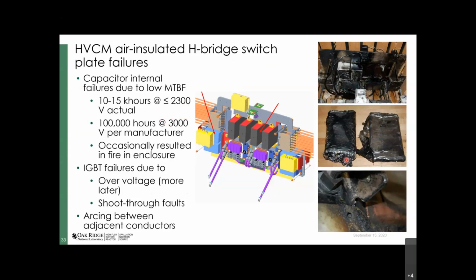What appears to be happening is that these are film-foil capacitors, and when they're wound, they have to be impregnated in oil, and occasionally you can get some bubbles trapped in there. It looks like in a lot of cases, some of those defects over time eventually lead to partial discharge and corona, which would cause the insulation system to fail. This is the inside of one of the capacitors after it had been damaged. Normally the pad, when they wind it, is quite flat like this. This one had arced internally and evolved a lot of gases, so basically it ballooned out.